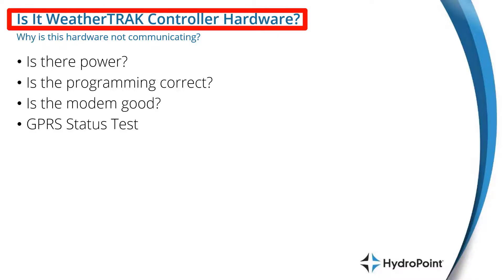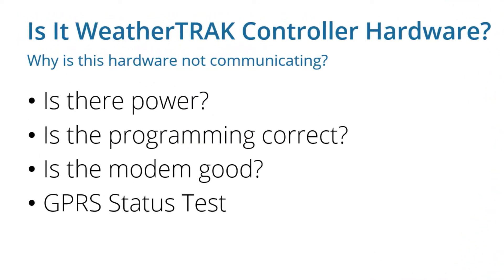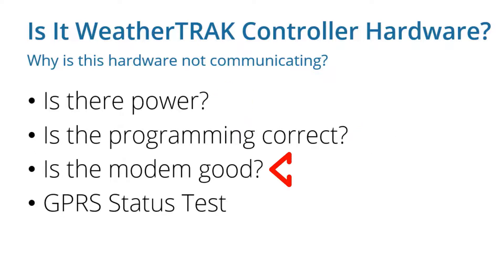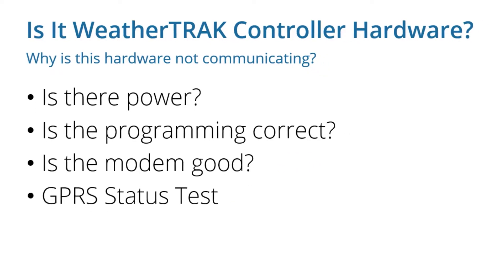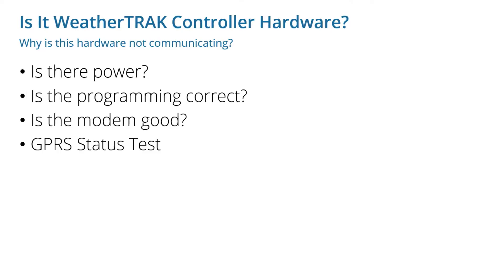When examining whether it's the WeatherTrack controller hardware that's at the heart of your communication issue, we want to diagnose, first of all, if there's a power issue; second, if the programming is correct; then see if the modem you have is current and good; and finally, be able to reset the modem with the GPRS status test.